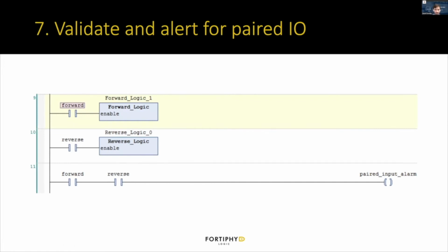Looking at a simple example here in CODESYS, maybe we have a forward and reverse variable. When the state is in forward mode, you execute some logic for forward, and in reverse, you execute some different logic. You can just add some checks there so that if the forward and reverse variables are both active at the same time, you raise an alarm saying, hey, it shouldn't be like that. Something's wrong here.